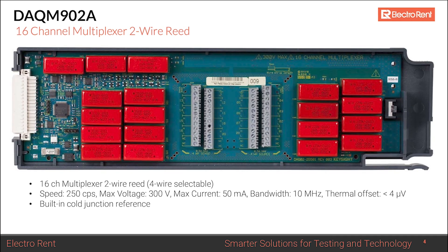The DAQM902A is a 16-channel multiplexer also using reed relays, scanning faster at 250 channels per second. You can use it for thermocouples, but the thermal offset is less than 4 microvolts — not ideal for high accuracy thermocouple measurements. It does have a cold junction reference, so it could serve as a backup thermocouple card, and it's also well-suited for four-wire measurement situations.